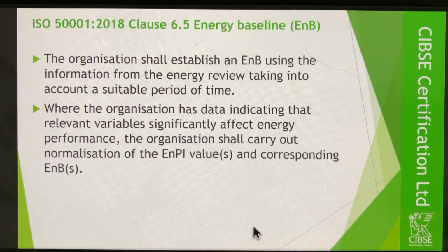Relevant variables significantly affecting energy performance. Well, I've already mentioned degree days. It's fairly well established that there's likely to be a link between your heating fuel use and the outside temperature. So that makes it a relevant variable. But don't assume that it will be a relevant variable. It's likely to be, but it might not be. We'll come to that later.